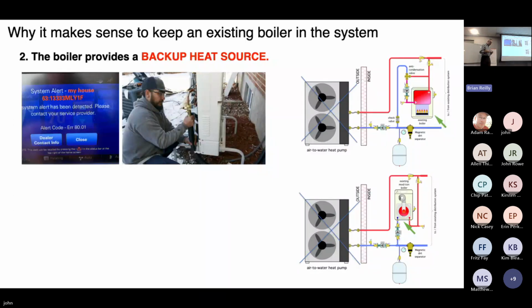Now, we were just talking during the break. There's a lot of new product coming into the market rapidly. And I looked at a lot of it. It's good stuff, but there's a lot of stuff in an air to water heat pump, as there is in a water to water heat pump, and even in an air to air system today. There's a lot of circuit boards. There's a lot of sensors in there. And the question is simply this: you're a homeowner, you've installed an air to water heat pump, something happens to it. Maybe it's as simple as a thermistor sensor, which is a $5 component, right? It fails. You're going to call the company that installed it. How quickly can they replace that component? If they have it in stock, or if the local wholesaler has it in stock, it should be as routine as a boiler nozzle replacement. Okay, but the question is, do they have it in stock?